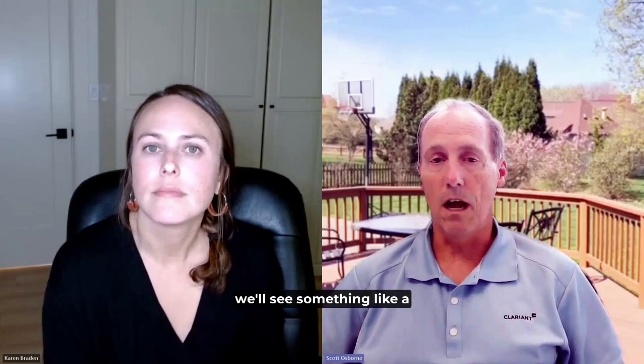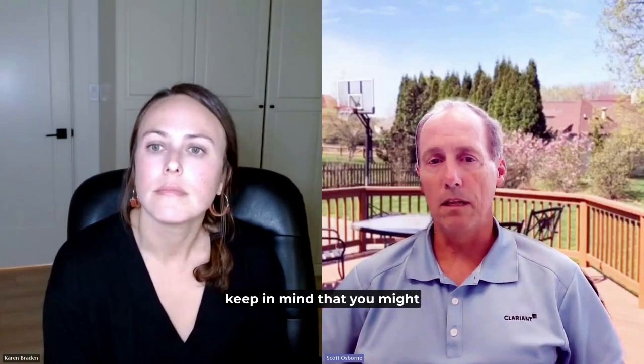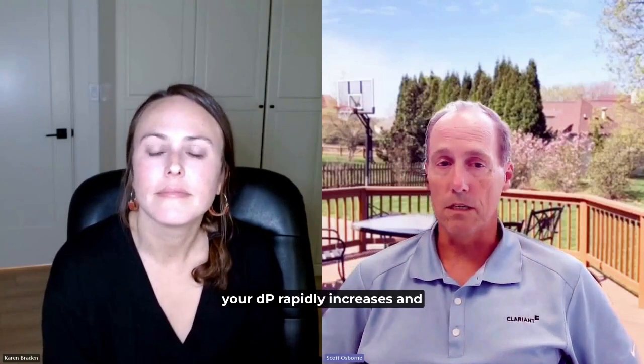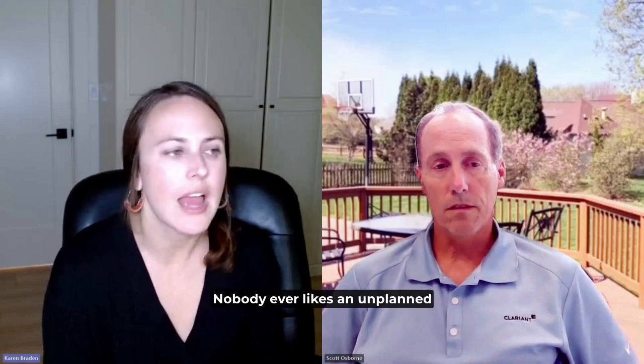Typically, we'll see something like a hockey stick rate increase on DP once you hit around the 35 to 45 psi level. So as your DP is climbing, keep in mind that you might reach a point where the slope of your DP rapidly increases and you're going to be forced to shut down and replace maybe before you're ready. Good point. Nobody ever likes an unplanned turnaround.